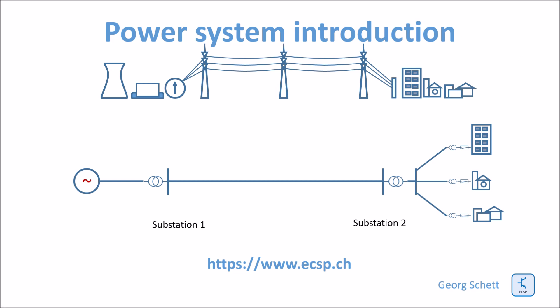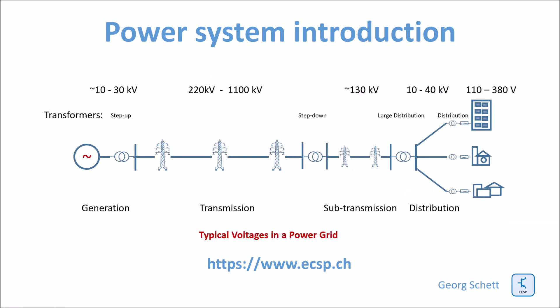The single line diagram shows just one phase instead of three. We have the generator, then the transformers at both line ends, then the line, and connections to loads. This is an example of typical voltage levels in a power grid. Generators feed at 10 to 30 kV, then a step-up transformer feeds the long-distance transmission network. The voltage level on long-distance transmission networks is between 220 kV and recently 1100 kV, such as in India and China where they have very long AC transmission networks.